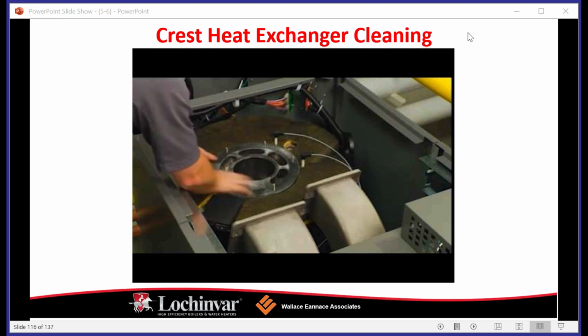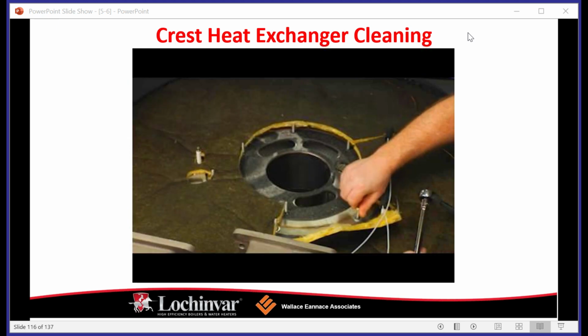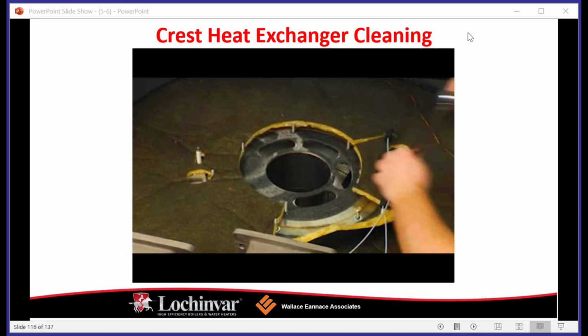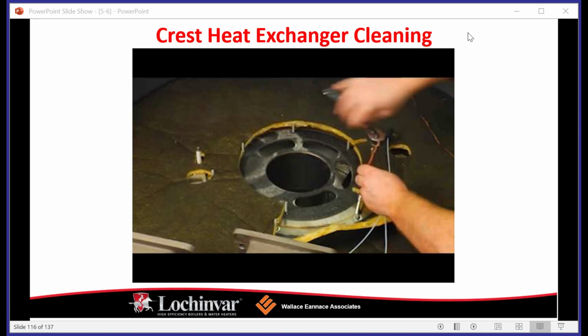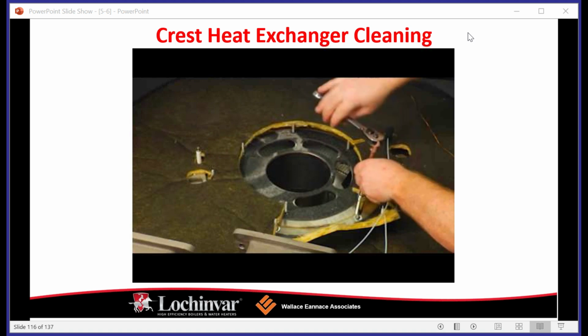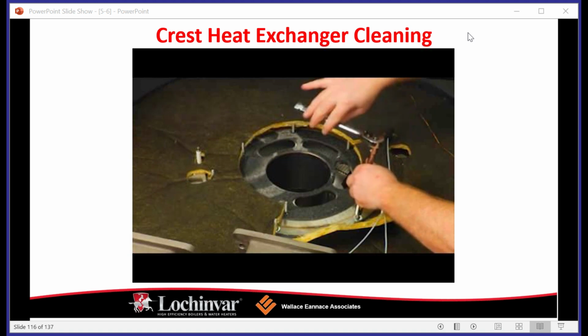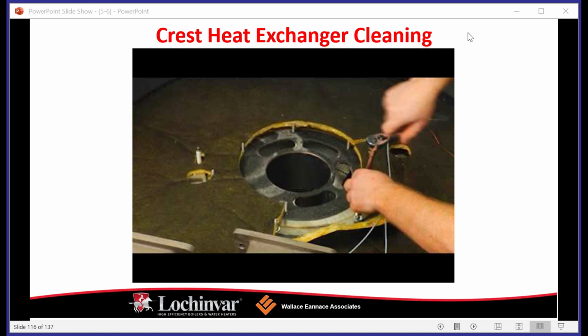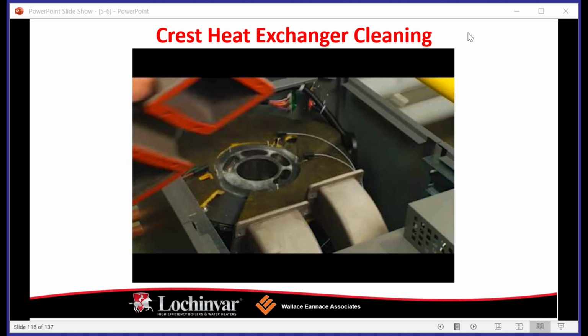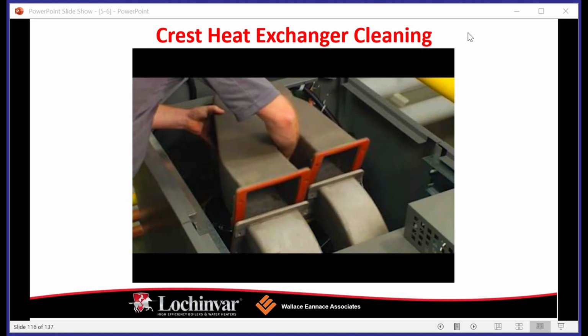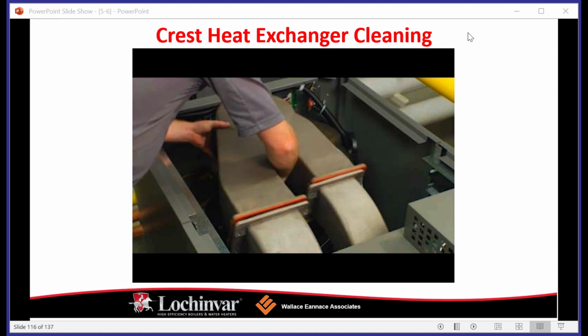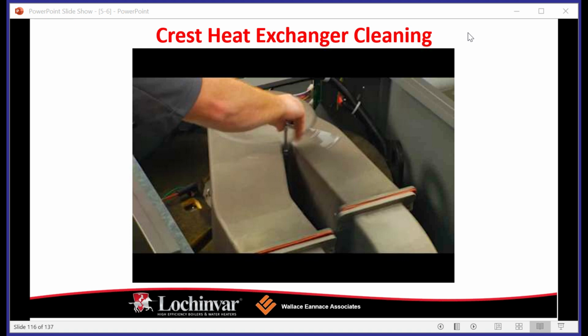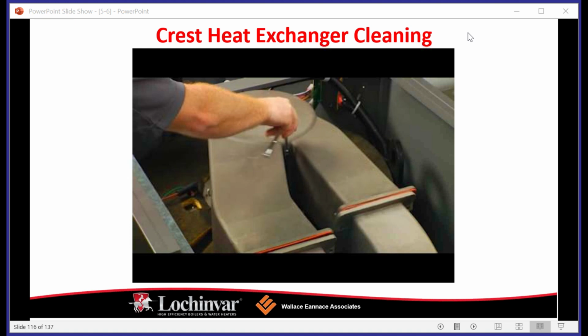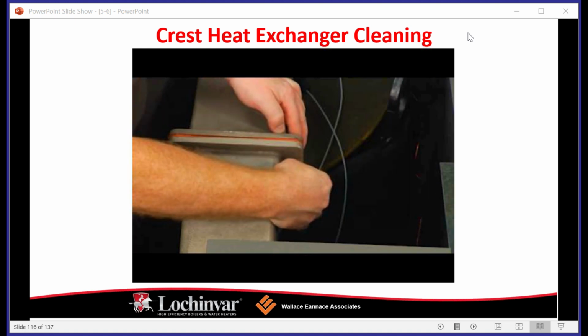A gasket is used to seal between the gas-air manifold and the burner. Care must be taken not to tear or damage the gasket. If the gasket is damaged or torn, then it must be replaced. For the 3 and 3.5 million BTU models, remove the 8 nuts securing the burner to the heat exchanger door. Pull the burner up and away from the boiler. Use caution when removing the burner to prevent damage to the refractory mounted on the inside of the heat exchanger door.